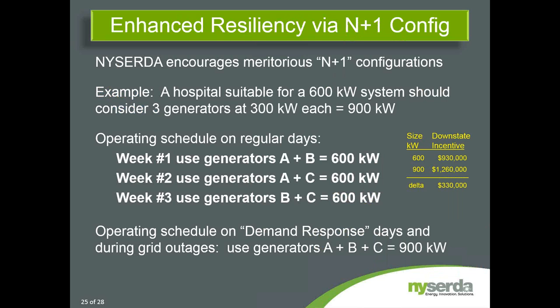We're also encouraging customers to install what we consider an N+1 configuration. If it's suitable for them to put in a 600 kW system, we encourage them to put in three 300 kW prime movers. So really it's a 900 kW system, but they dispatch only 600 kW at any given time. That will make the equipment last longer.